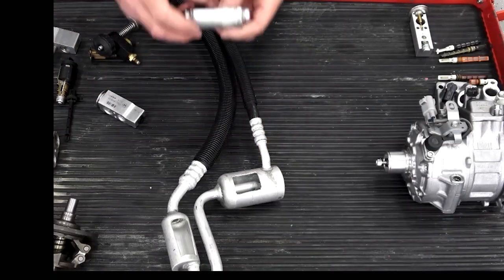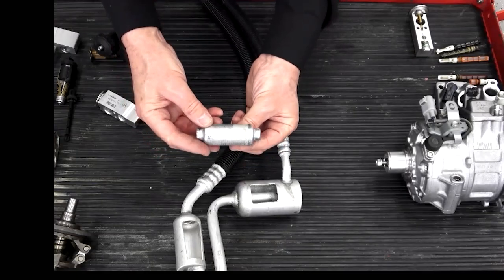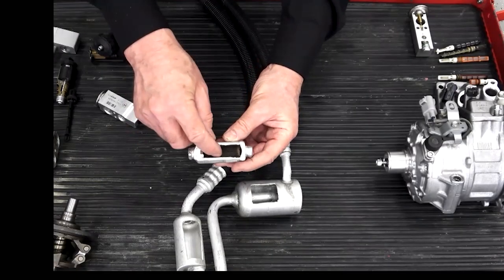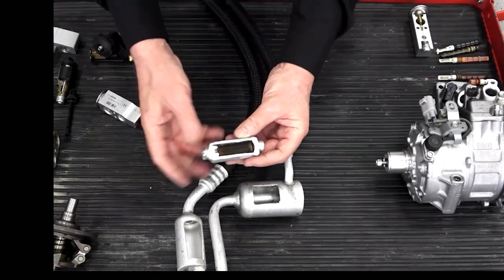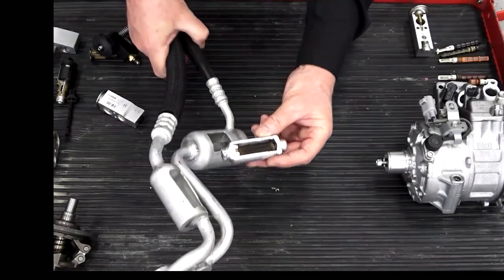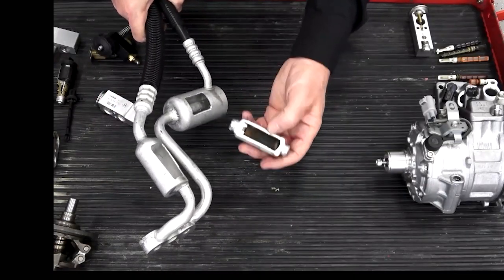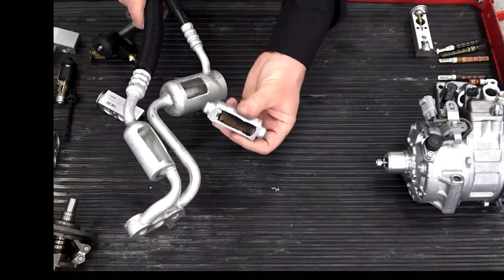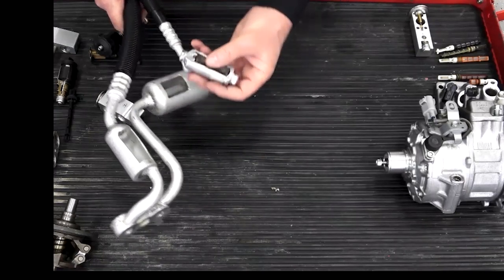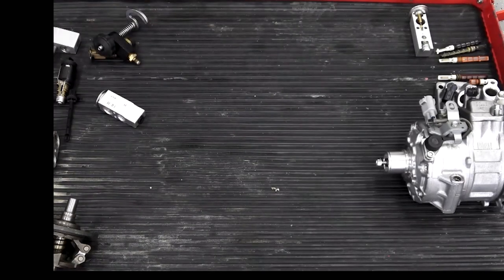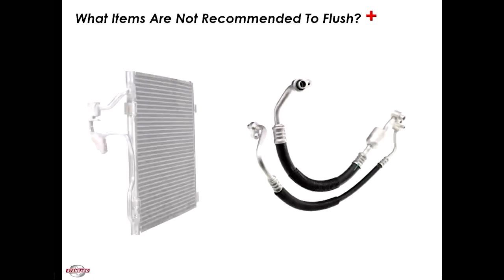Here's one, this bubble here, looks like it's just a bubble in the line, but inside of it is a paper filter. Again, this was an actual case study we had here years ago. If the lines have a bubble or some kind of a thing that looks like any of these in the hose, in the line, and the compressor has failed, I highly recommend that you replace the hose assembly rather than trying to flush it.